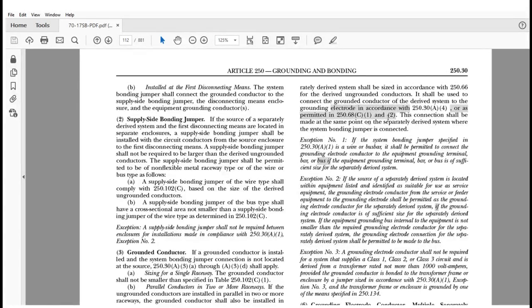The other part that I think is really important to remember is this part here that was added in item 5. It says that it shall be used to connect the grounded conductor to the derived system grounding electrode in accordance with 250.30(A)(4). We get that. But it says, or as permitted in 250.68(C)(1) or (C)(2). And that is saying that those two items, the metal water piping and the structural metal framing, as covered in 250.68(C)(1) and (2), can be recognized as conductors to extend that connection to the grounding electrode. Okay, so they're basically saying they can be used as conductors. All right? And of course, you have to meet all the requirements in 250.68(C)(1) and (2) to do this, but it is putting that language in place for you to be able to establish that. So that was a significant change there.